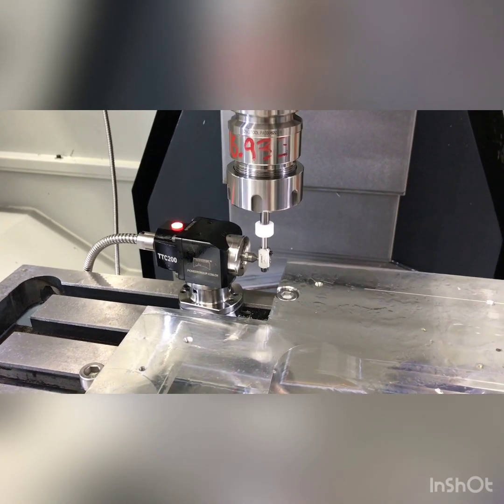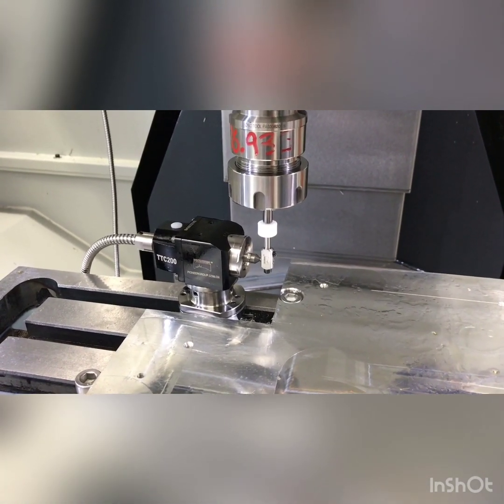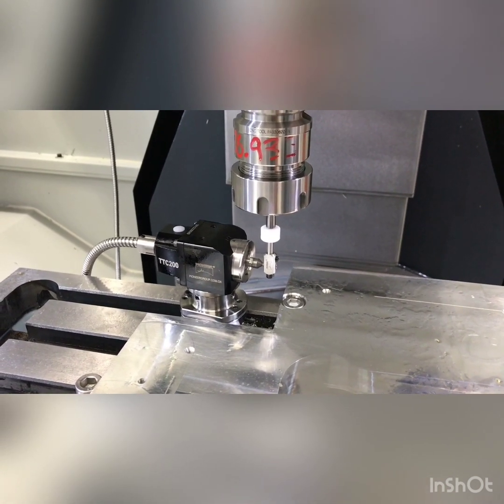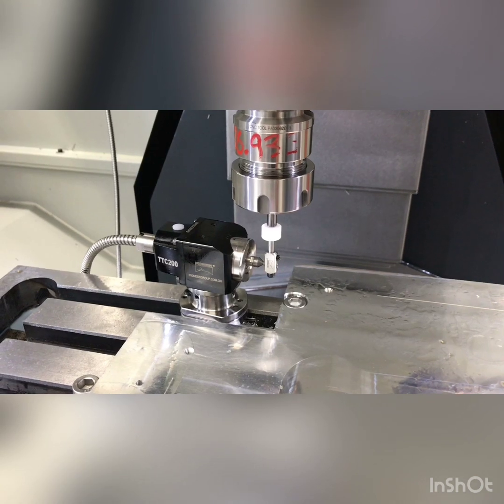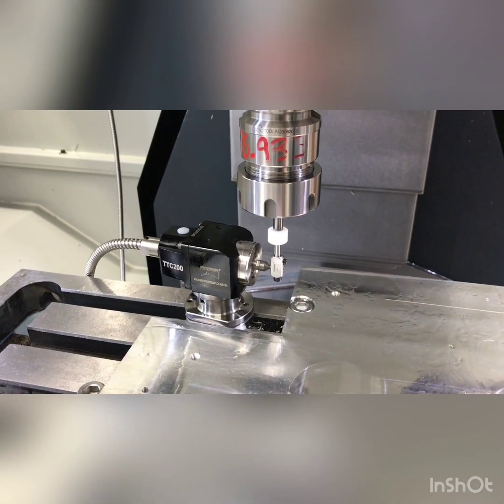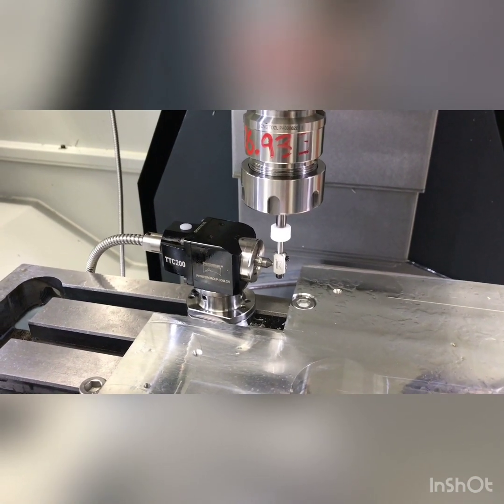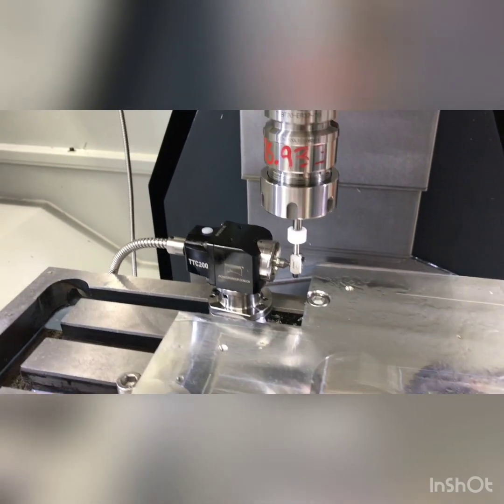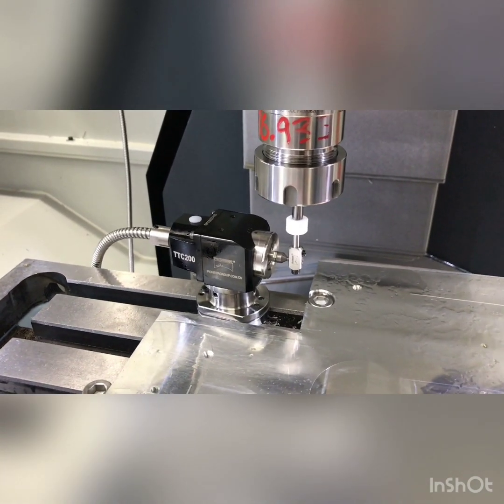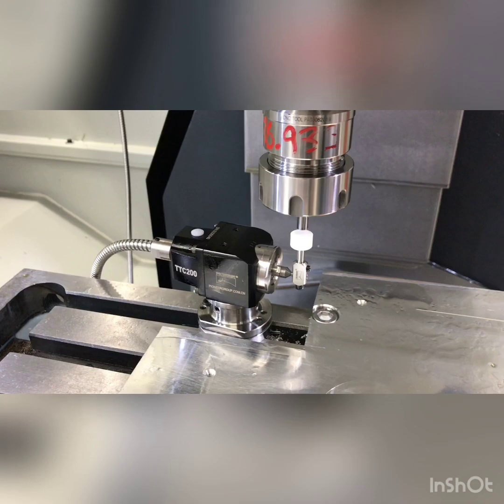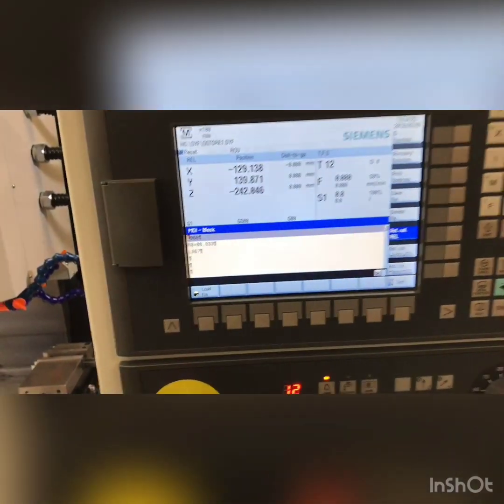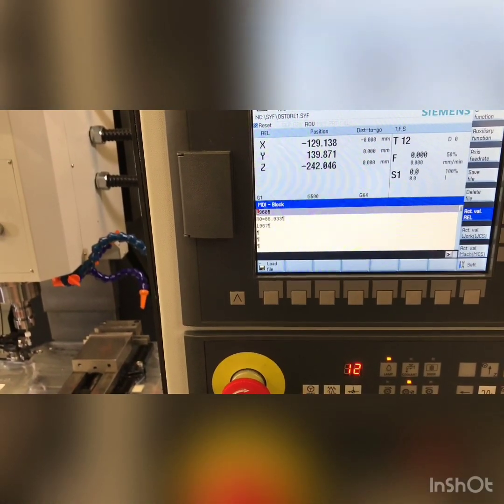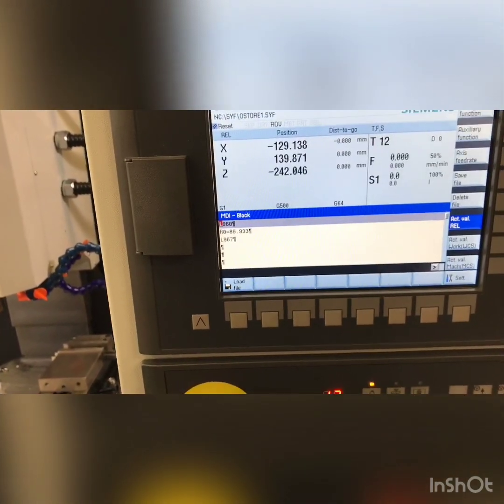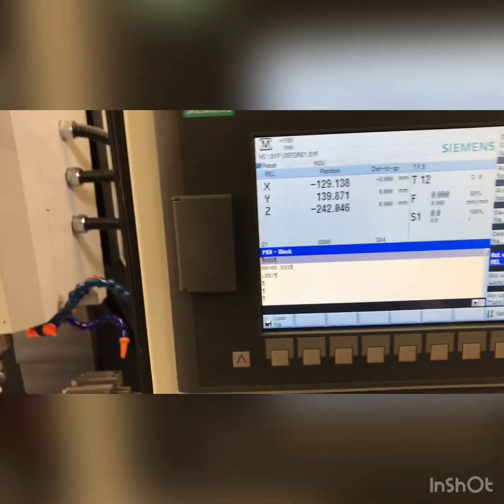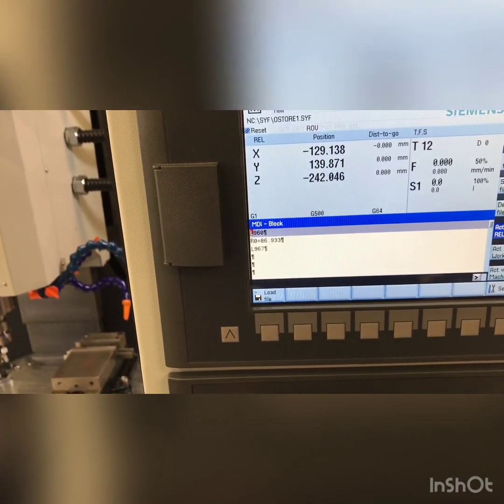So 1 hit, 2 hits, and I've got the feed rate at 50%. I'm not sure how big of a difference that'll make, but the last measuring is very slow. So I'm assuming it averages between all three, and that's it. So that's set. Now the next thing we need to do is calibrate the diameter of the probe, so that is to find the center of it. So I'll reprogram that and get set up again, and then we'll do that one.